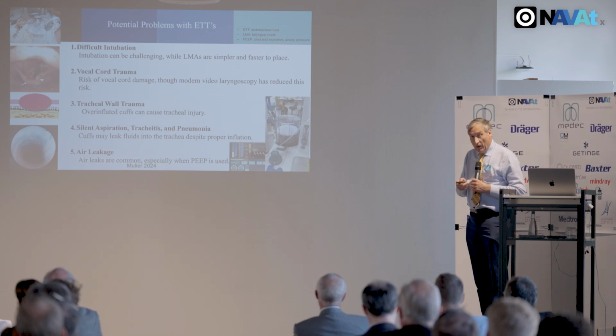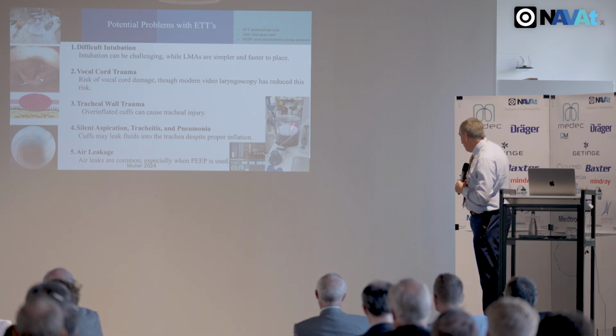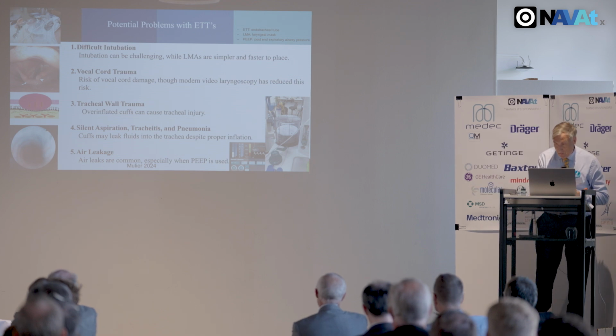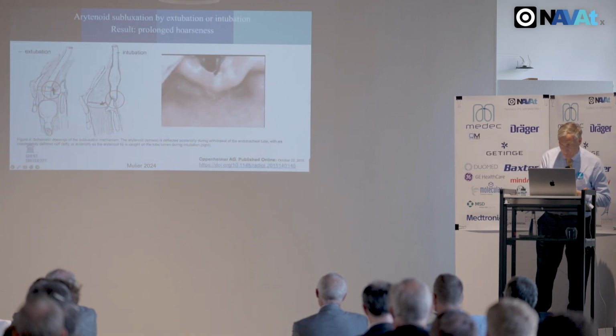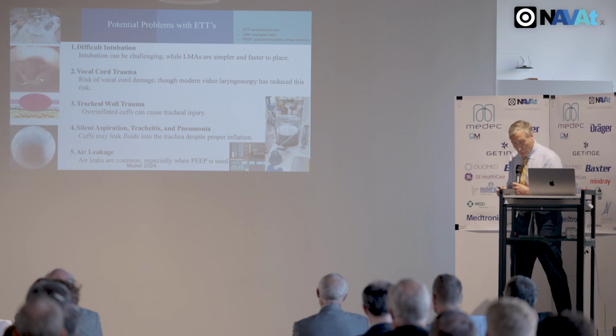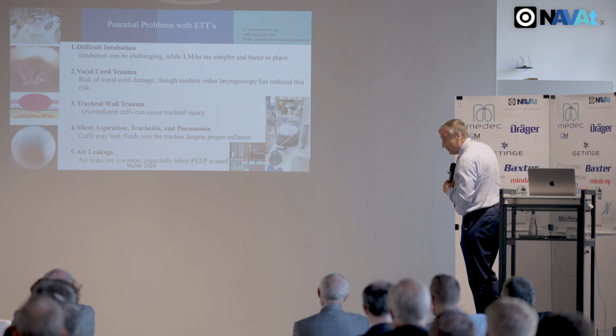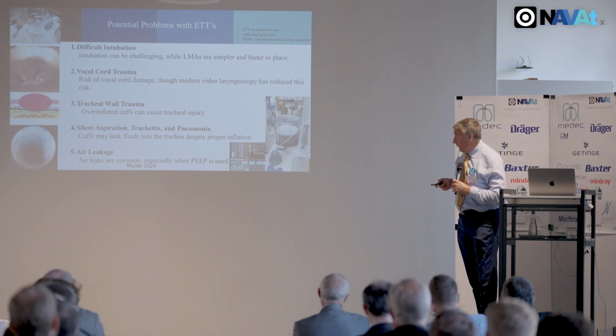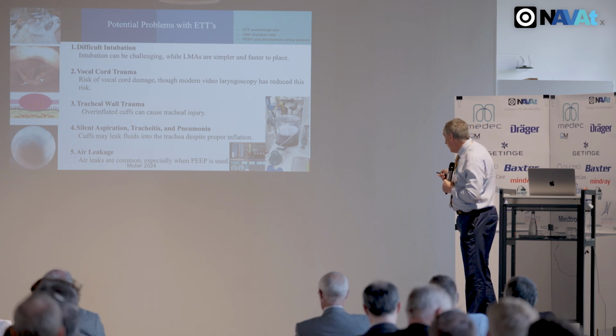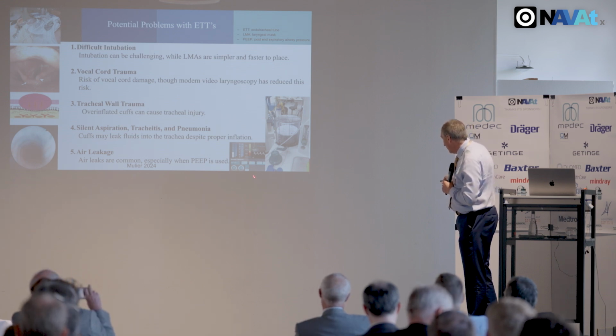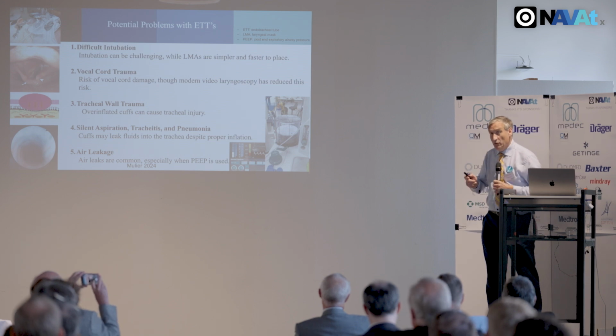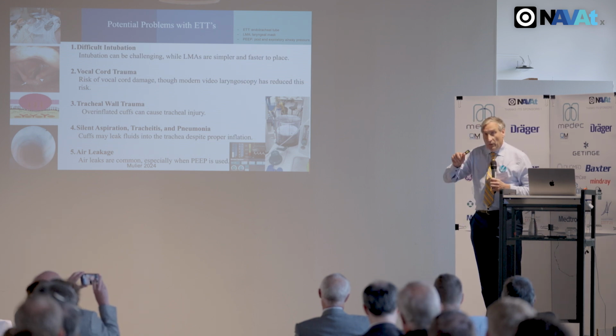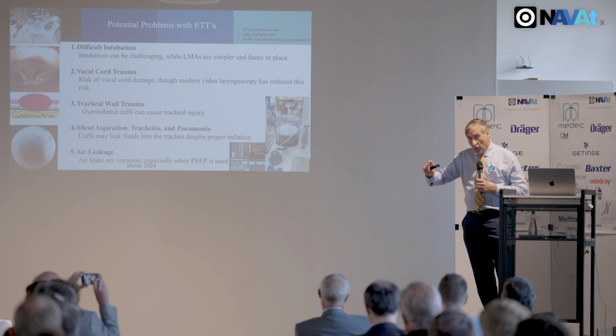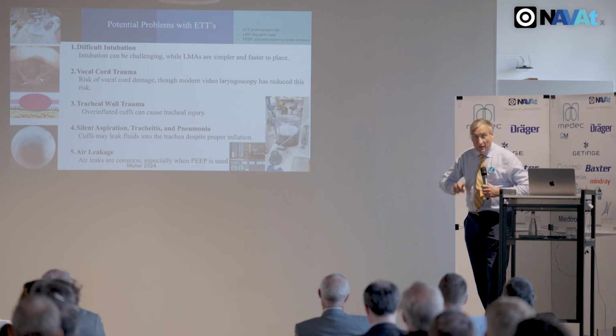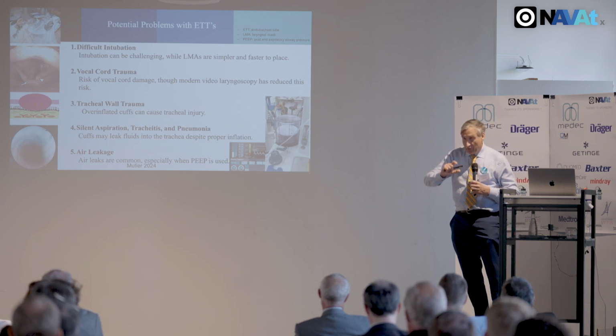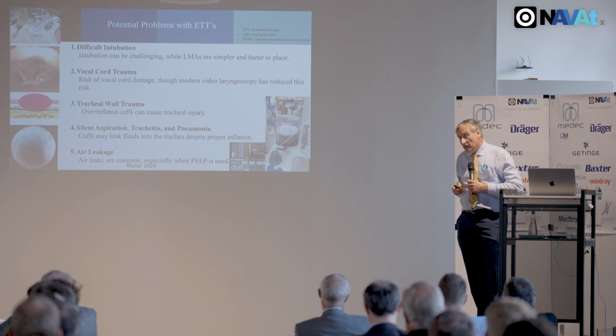Now, air leakage, you can find that on your ventilator, and certainly if you look here, you will see that the ventilator bellows is not coming up to the full position. It means that your fresh gas flow is not enough, even at half a liter or 1 liter. Other ventilators, like the Dräger, shown here in the red zone, meaning your fresh gas flow is not enough. Now, most ventilators will measure the inspired and the expired tidal volume, but for a long time I have been asking, just give the figure of the leakage, even in liters per minute. That would be very easy.